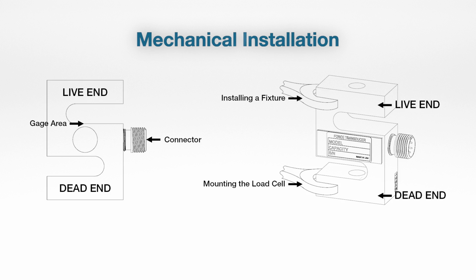All right, so this is a good depiction of live end versus dead end. You'll notice that the cable and the mount surface are separate from the live end of the load cell. So we would want to make sure that the load, or what you're trying to measure, is applied to the live end, and that you'll be mounting to the dead end of that load cell. We don't want the cable or the mounting surface to somehow impact the measurement you're trying to take. In installation here, if you're working on installing a fixture, you can see the depiction here. You want to make sure that you're not transmitting any torque through the gauged area and potentially damaging the gauges through any moment being applied.